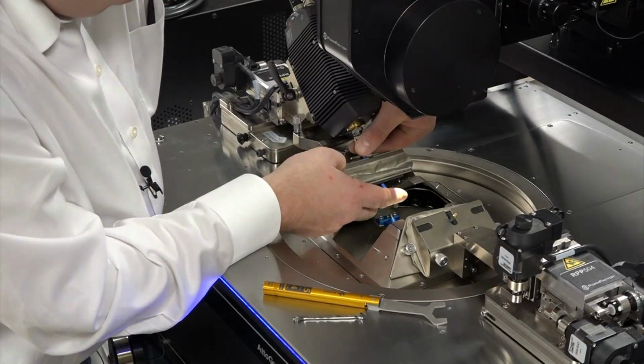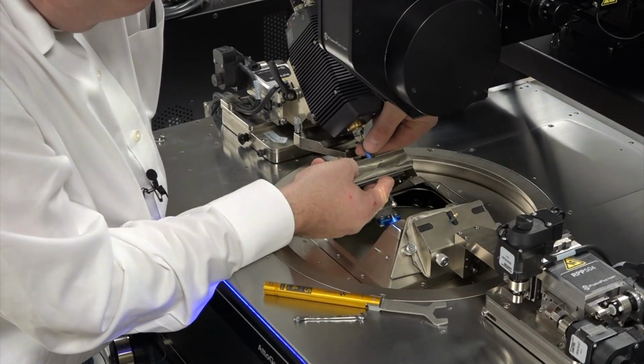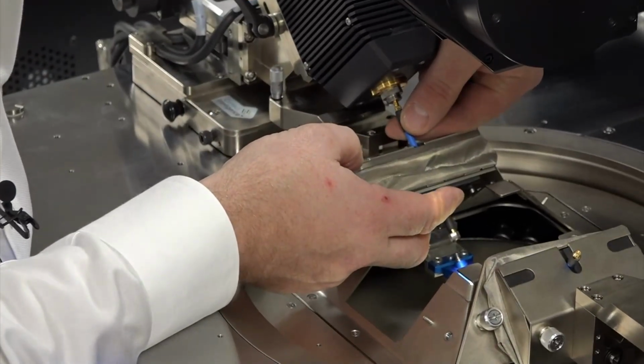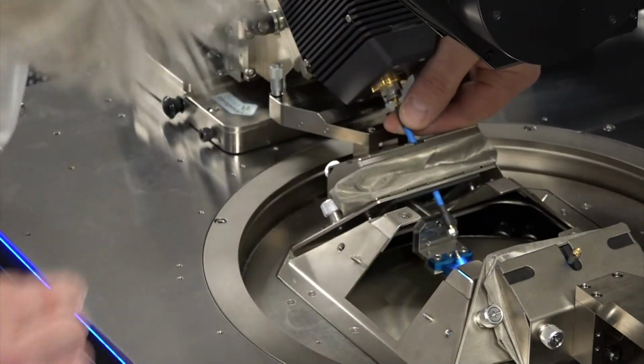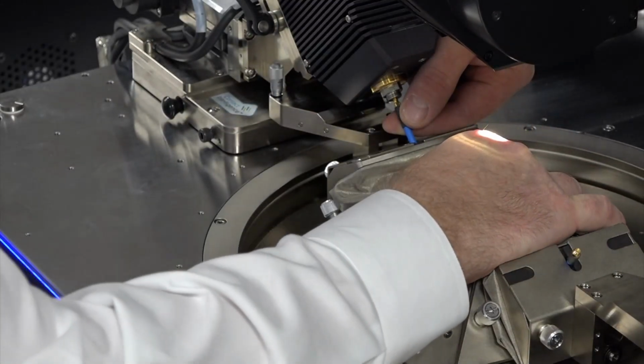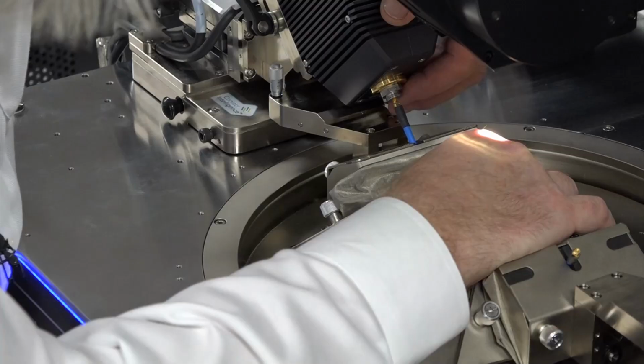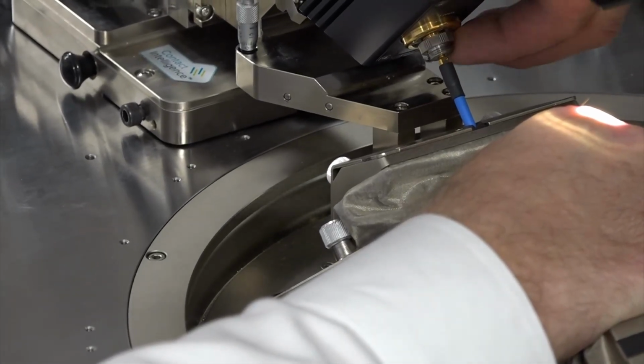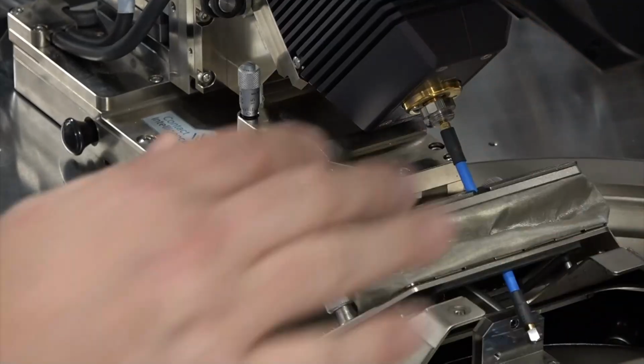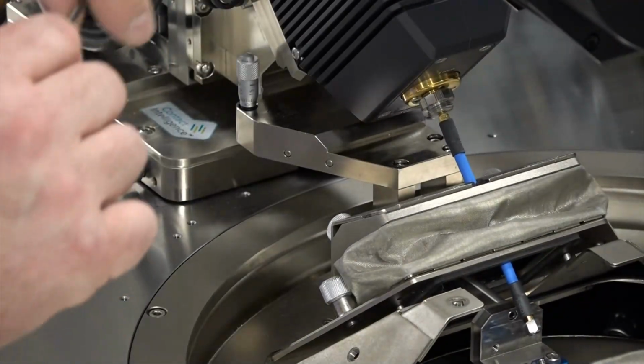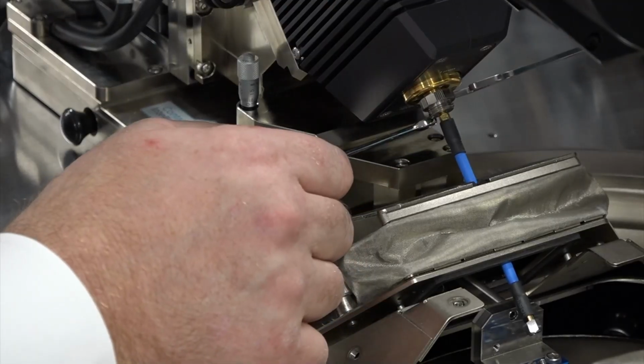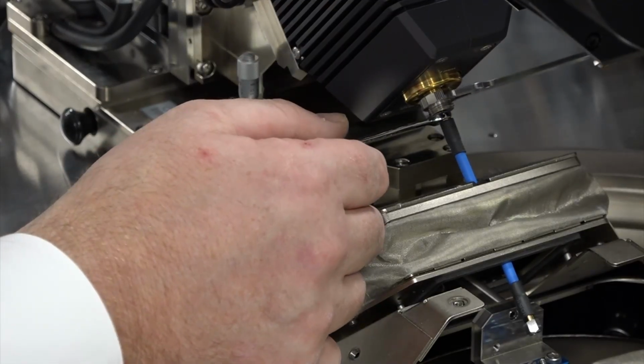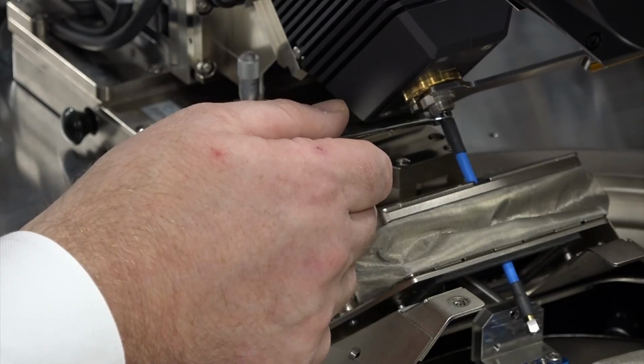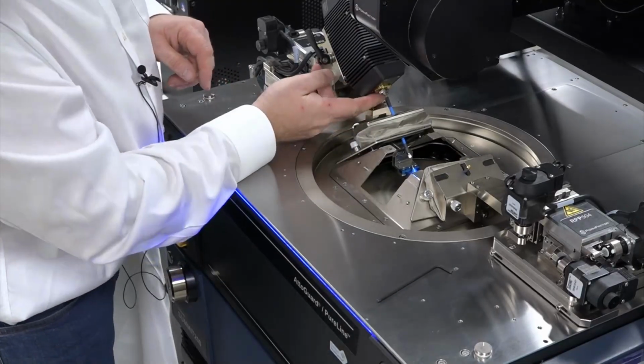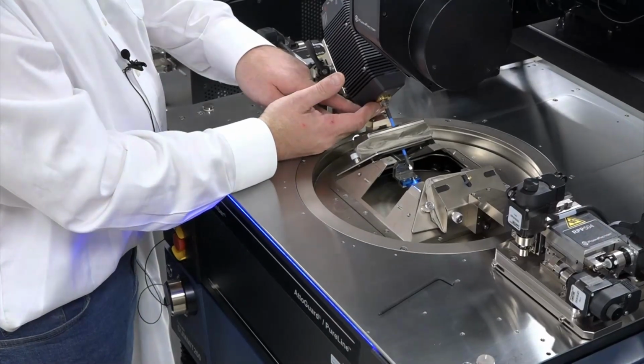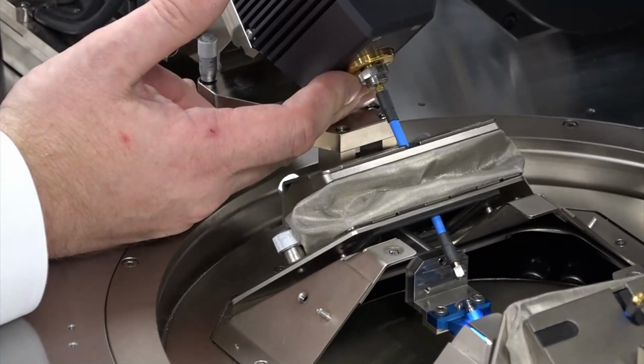So I'm going to just get the cable, making sure it's clear of the probe. Nice and straight. It's generally go towards most of the way to the top. I'm just going to push it. I'm going to hold it down. And I'm going to just push that in nicely like that. I'm going to get the torque wrench. Don't forget my spanner in there. And just torque the cable end up. I'm going to put one finger or a couple of fingers underneath the frequency extender. Make sure you do this because it wants to slide forwards.